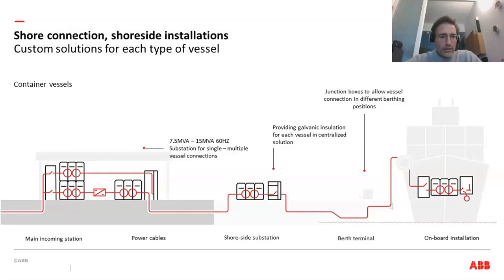The solution can be dedicated for one single vessel or centralized. In this case, we need galvanic insulation for each vessel. Onshore, it's different from cruise because the cable management system onshore is basically nothing on the berth - there are only pits with plugs and sockets, and it's the vessel that has the cable management system. So it's typical of container vessels to have the cable drum on board.